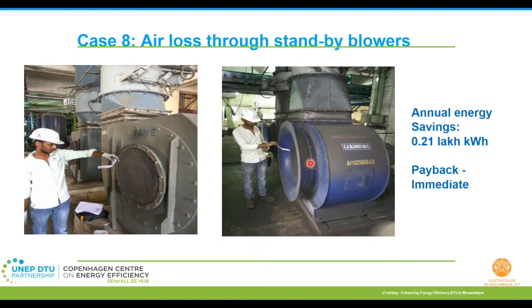When we actually measured the air flows and pressure requirements, I don't have to complicate things with flows and pressure, but just look at the cloth here, which is trying to get sucked into the blower inlet. That means the blower was operating. It was sucking in air and trying to release it into the conditioned space. Since there is another blower on standby mode connected in parallel to this, and both share the same duct, a part of the air is circulated back to the non-operating blower and pushed out. So a certain portion of the air for which the blower is working is wasted because most of the air is actually coming back to the same place. If you look at the cloth here, it is getting blown away.